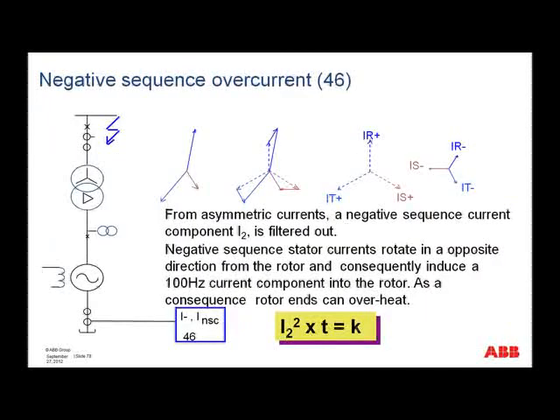Negative sequence overcurrent. So here from the asymmetric currents, we can filter out the negative sequence. If we have asymmetric currents, then of course we can calculate negative sequence. Now, why is negative sequence hazardous to the rotor? It's hazardous to the rotor because it rotates in the opposite direction. So it induces 100 hertz, or I guess 120 hertz in the 60 hertz system, current component into the rotor, and as a consequence the rotor ends can overheat.